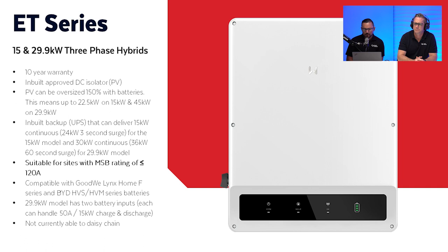At the moment, these new larger hybrids are suitable for sites with a main switchboard rating of 120 amp. The reason for this is it comes with an energy meter in the box that has 120 amp CTs, and at this time GoodWe don't have an energy meter that will allow you to use your own larger CTs. However, they're working on this.